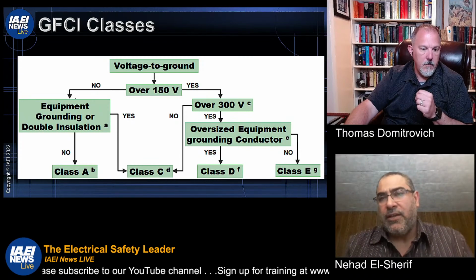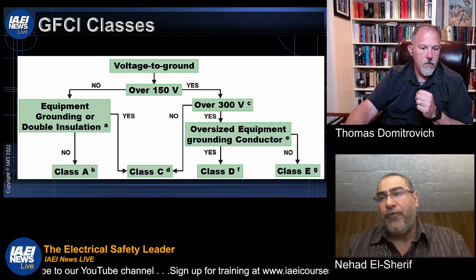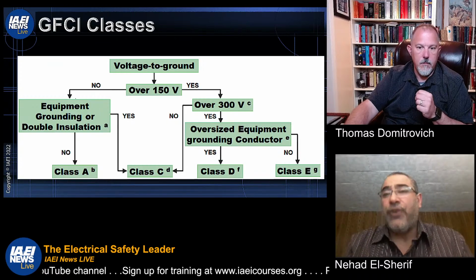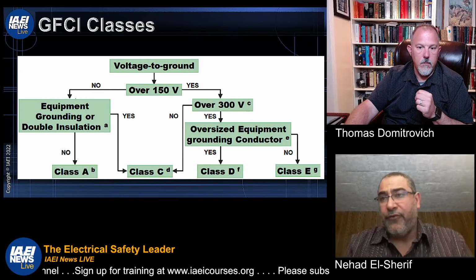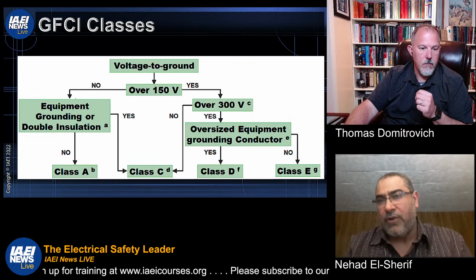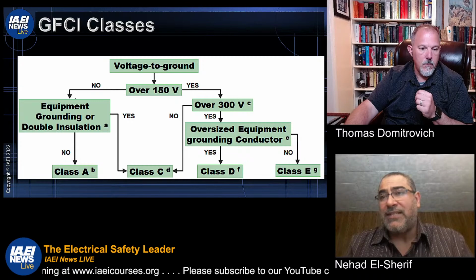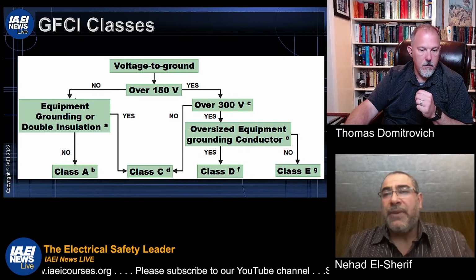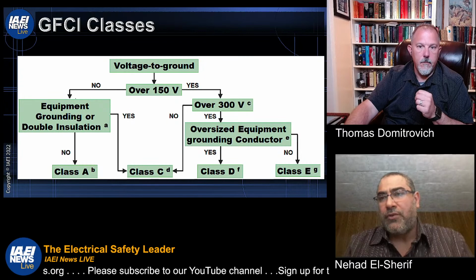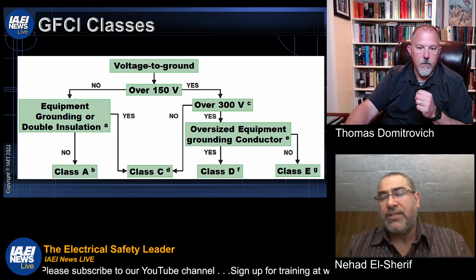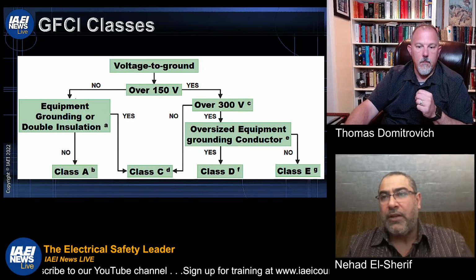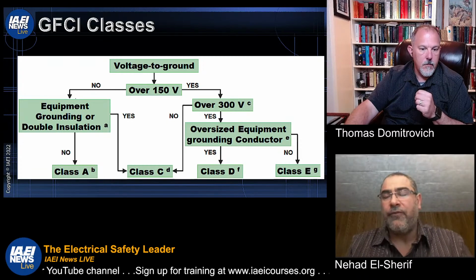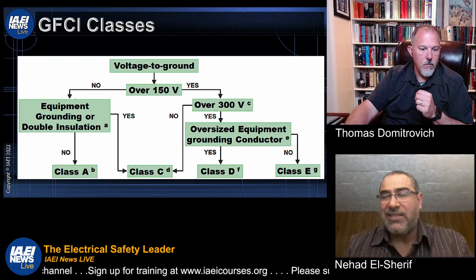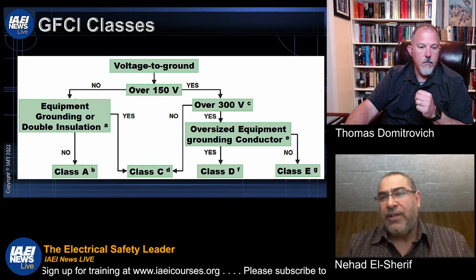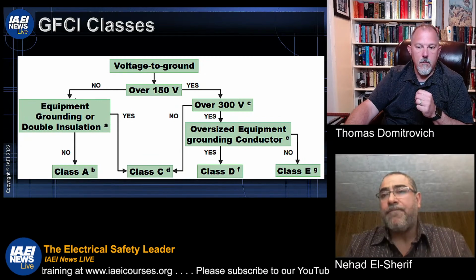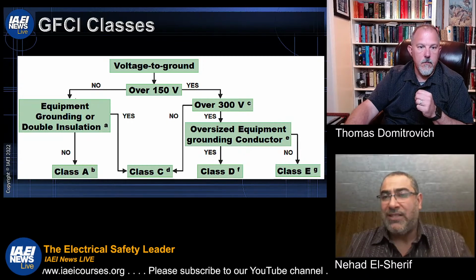The interesting thing is when you have an application that is over 300 volts to ground. I guess 480 volt as well: you can get Class C for 480 volt applications, because the line to ground for a 480 volt system is less than 300 volts. It becomes interesting, and this applies more to 600 volt systems, which are mainly in Canada more than the US. The US is 480 volt distribution voltage, so you'd be pretty safe using Class C most of the time. But when you get to a voltage to ground higher than 300 volts, UL has a distinction between a Class C and a Class D.